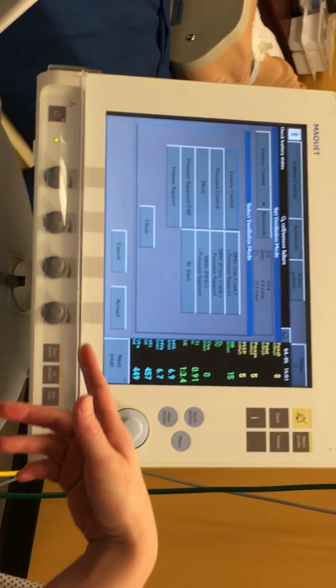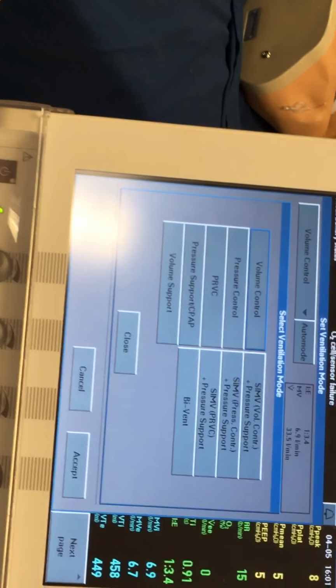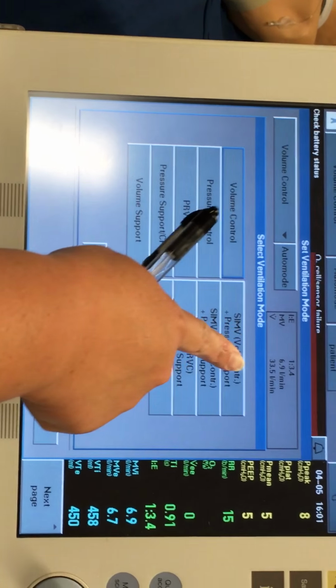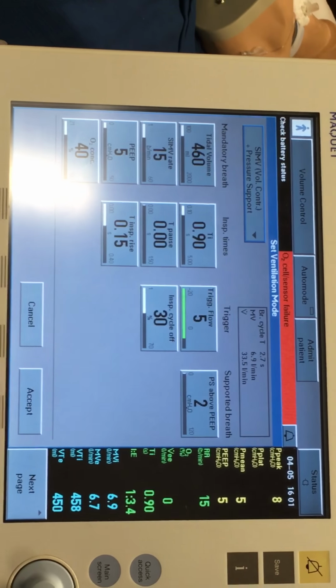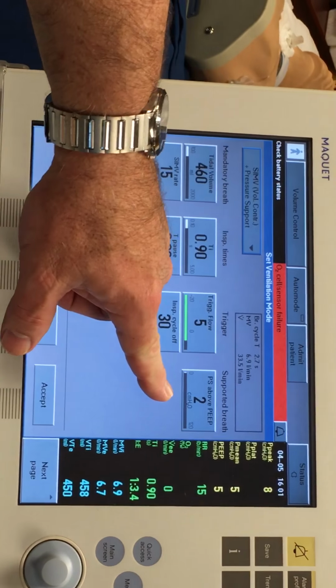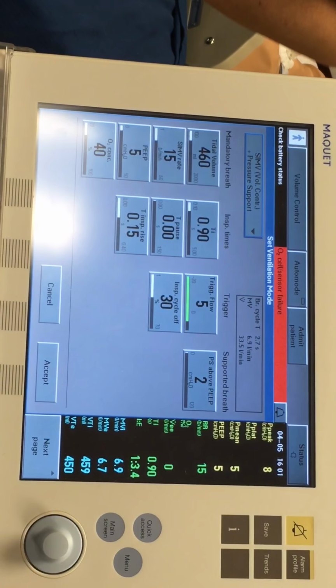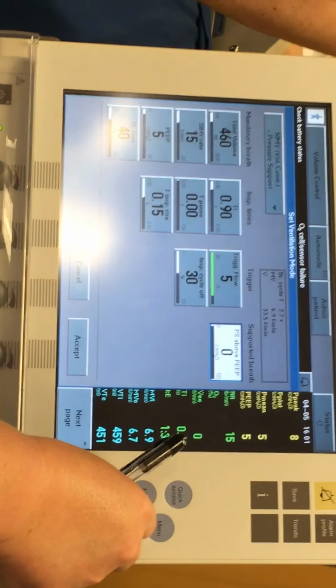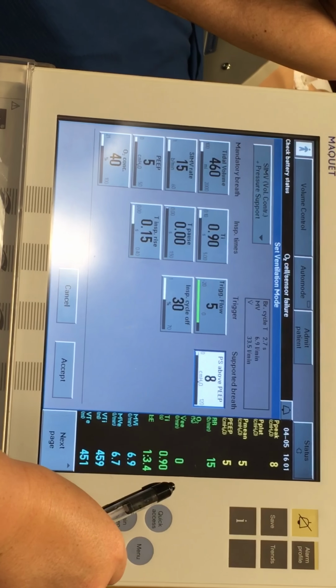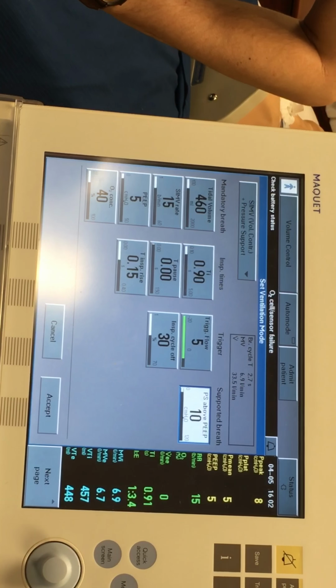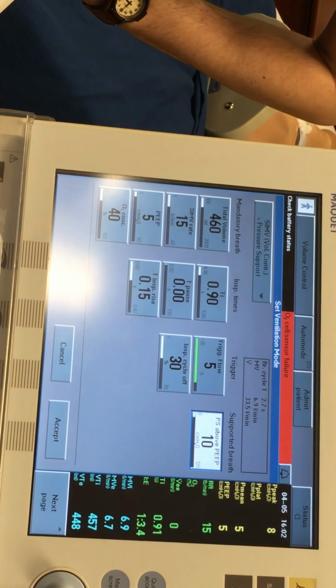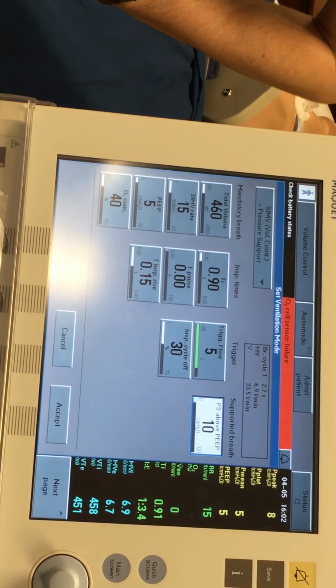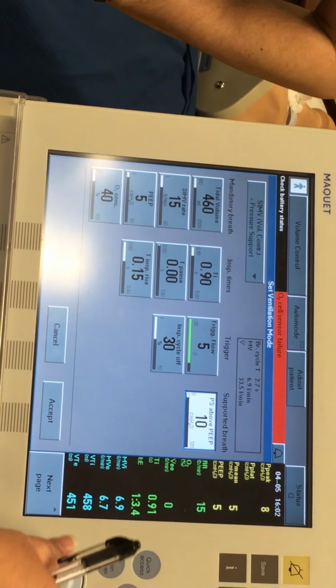So Bivent is APRV, right? Okay. I wanted to clarify that in SIMV volume control with pressure support. And notice how this is your pressure control knob here, and it says pressure support above PEEP. So when you look at your peak pressure, say I'm on 10 of pressure support and I'm on 5 of PEEP, my peak pressure for a spontaneous breath should be 15. That's why it says above.